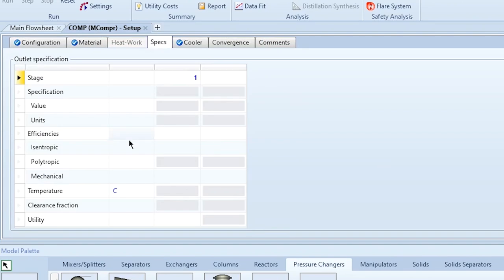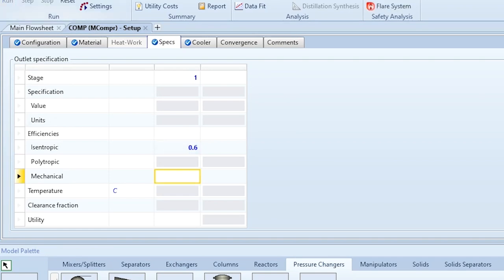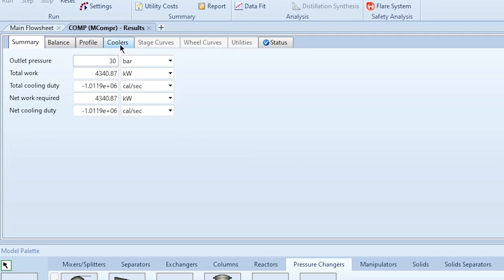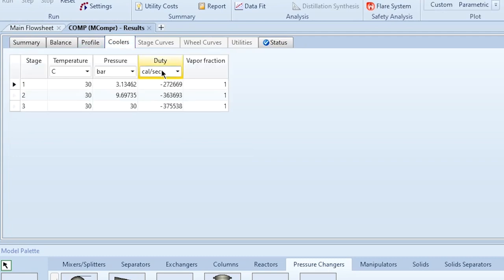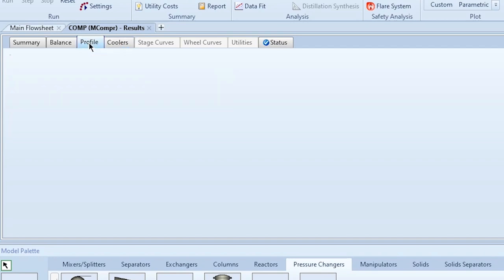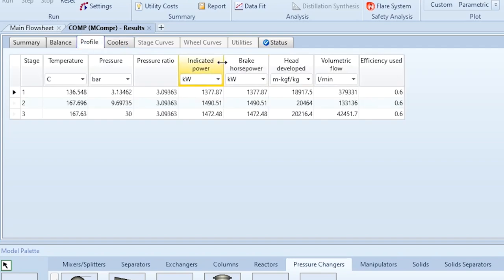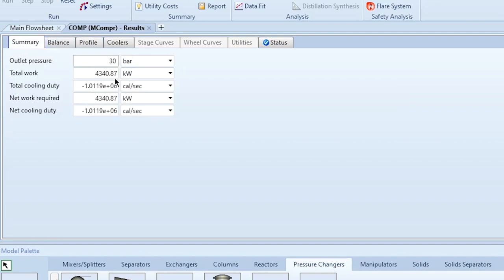If you want to specify a custom compression efficiency, enter it in the configuration — for example, 0.6. Click Run again. Going to the Cooler results, you can see changes: earlier it was around 900 kW, now it is 1141 kW. The profile shows efficiency of 0.6, with all results updated accordingly. There is a significant difference due to the lower efficiency. You can perform analysis by varying efficiencies and number of stages to optimize the system.